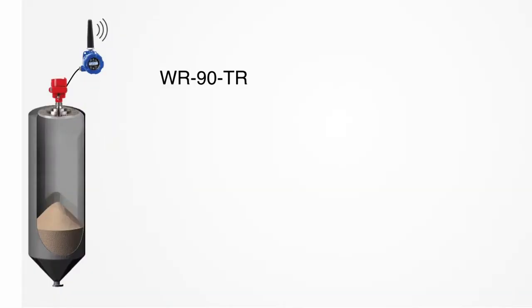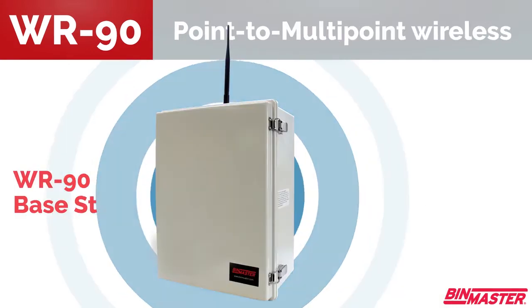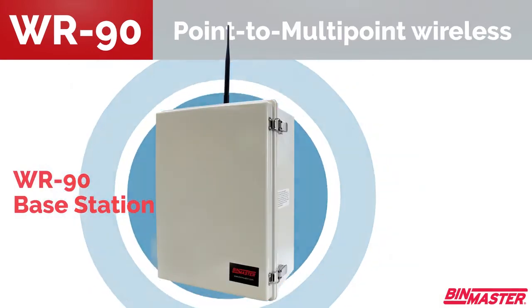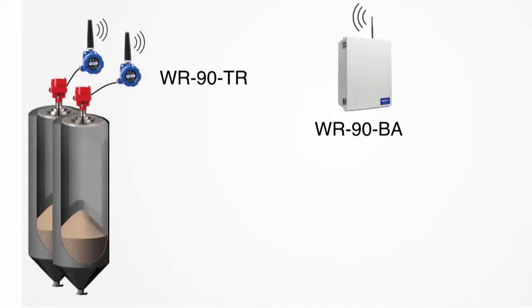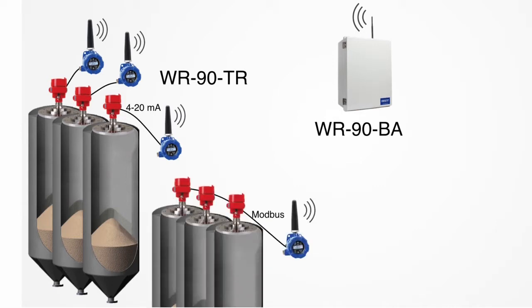And here you can see we start with just a sensor and the wireless transceiver, sending the data out to a base station, our WR90BA. And in this case, it happens to be a 4-to-20 unit, and it's got a single connection to the wireless unit, sending it over to the base station. But we can expand on that and add additional units. So we have additional 4-to-20 units, as you can see here, transmitting back to the base station. But it doesn't have to necessarily be 4-to-20 units. It could be Modbus units, and that's what you can see right here.